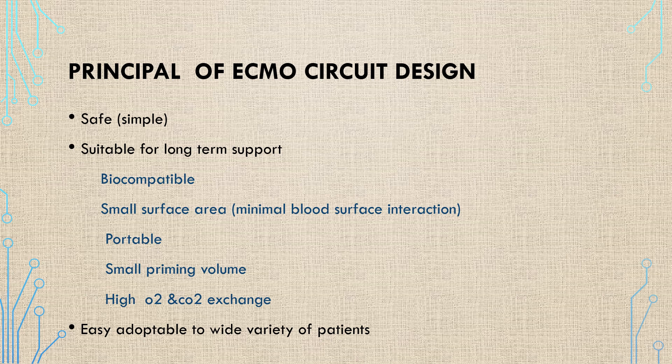The principles of ECMO circuit design should be: simple, no multiple connections, suitable for long-term support — which is achieved by surface coating to increase biocompatibility — small surface area, minimal blood-surface interaction, portable, small priming volume to decrease blood transfusion to the patient, high oxygen and CO2 exchange so the oxygenator exceeds oxygen demand, and easily adaptable to a wide variety of patients.